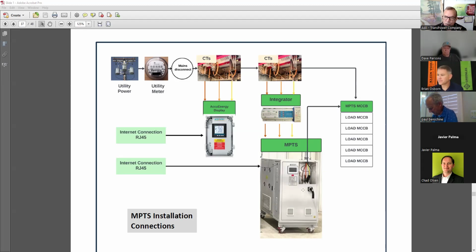Yeah, but you and I will always recommend that you have this MCCB shown on this sheet providing power to the MPTS, so that you have overcurrent protection inside the MPTS for, I think, 20,000 amps or 60,000 amps. Whereas this MCCB is another delayed - it's a few seconds delayed, but it's a second set of protection. If something happens inside the MPTS, you need that to make sure it doesn't go into the building.